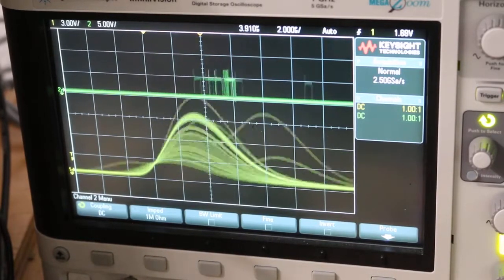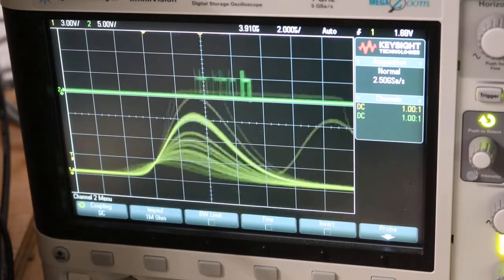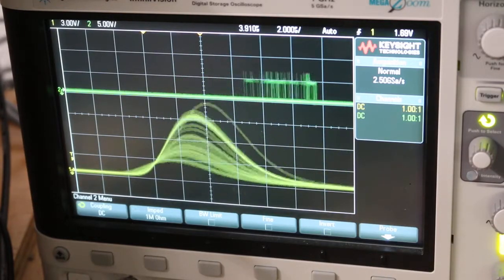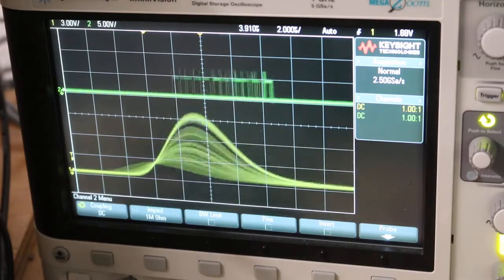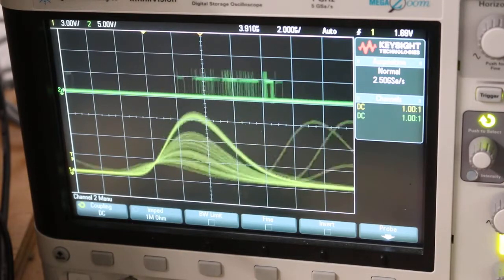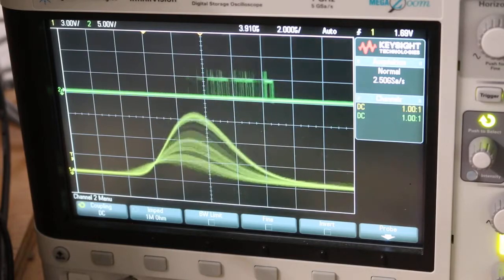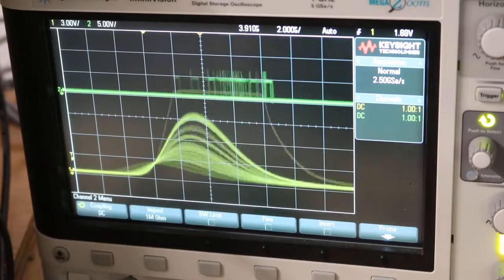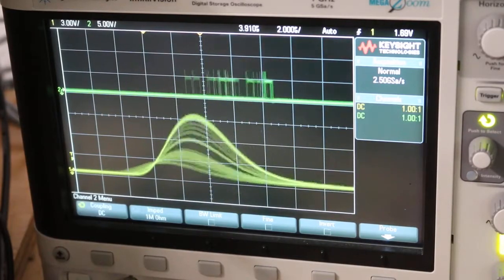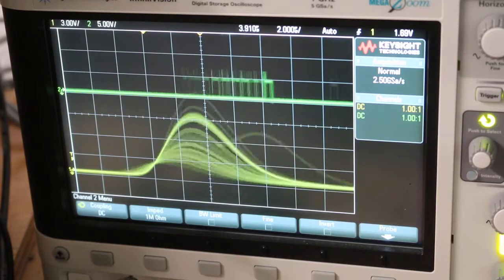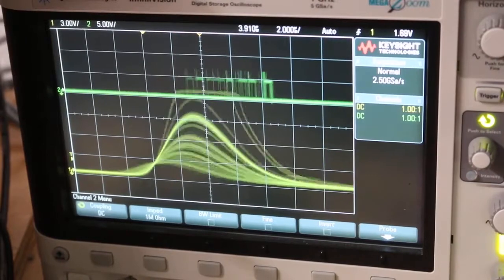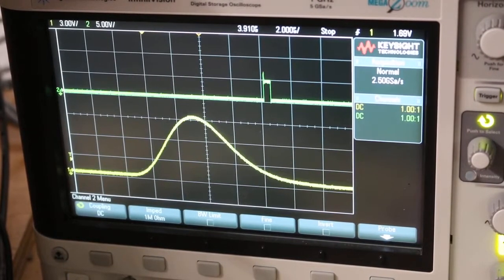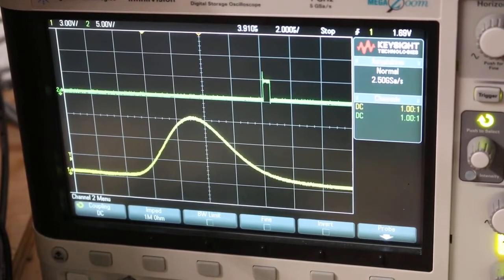So typically the way I'm going to use it at the moment here, I'm going to turn the low level all the way down, and the pulses look like a mess. Now I'll raise it up just a little bit to get out of the noise, and I'll just leave it there. And so I'm pretty sure now that I'm out of the noise, the stuff that exists way down at the bottom right there. I get one green pulse from the SCA for every one of these yellow pulses that comes in from the detector, one pulse like that every time.